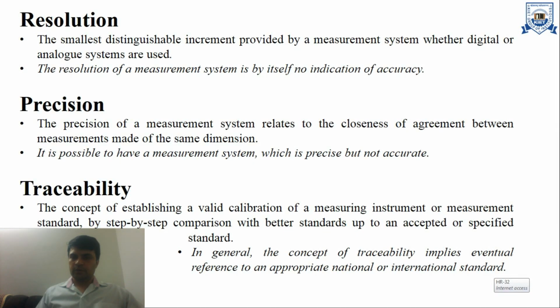Then we have resolution. The smallest distinguishable increment or smallest change provided by a measurement system, whether digital or analog, is known as resolution. It means the smallest increment in the input that may change the output. This is known as resolution. The resolution of a measurement system is by itself no indication of accuracy. Then precision. The precision of a measurement system relates to the closeness of agreement between measurements made of the same dimensions. It is possible to have a measurement system which is precise but not accurate.